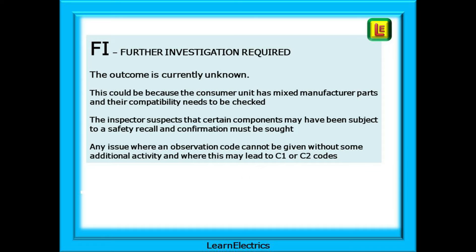And lastly, FI. The inspector has decided that further investigation is required for part of the installation — the outcome for this part of the inspection process is currently unknown. This could be because the consumer unit has mixed manufacturer parts and their compatibility needs to be checked, or the inspector suspects certain components may have been subject to a product safety recall. It is any issue where an observation code cannot be given without some additional activity, and where this may lead to C1 or C2 codes.